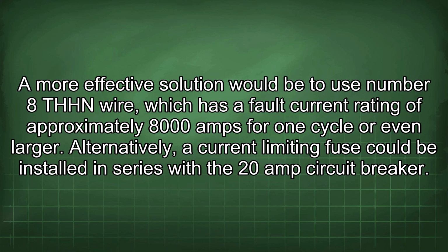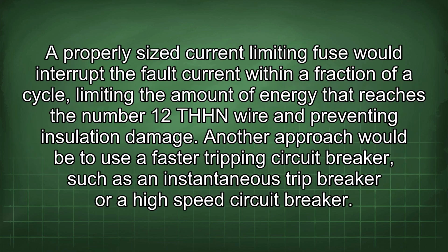Alternatively, a current-limiting fuse could be installed in series with a 20-amp circuit breaker. A properly sized current-limiting fuse would interrupt the fault current within a fraction of a cycle, limiting the amount of energy that reaches the number 12 THHN wire and preventing insulation damage.